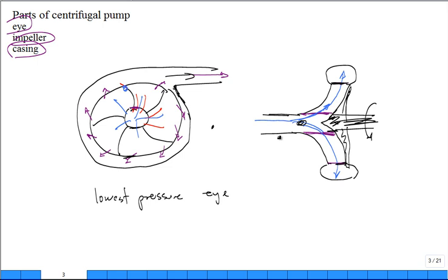In the vanes, this side right here is catching the water and it's high pressure. On the back side of the vane is really the region of lowest pressure. But we'll get into cavitation in a minute. Inside where those impellers are, some regions are very high pressure, some are low pressure. And then the discharge is your high pressure. That's where your highest pressures are. So the pressure on the out is greater than the pressure on the in.